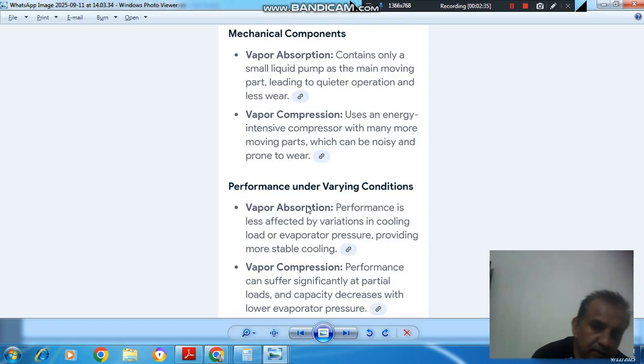Regarding performance under varying conditions, in vapor absorption the performance is less affected by variation in cooling load or evaporator pressure, providing more stable cooling. Whereas in vapor compression, the performance can suffer significantly at partial load, and capacity decreases with lower evaporator pressure.